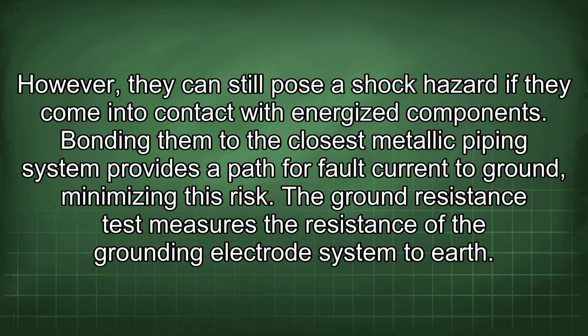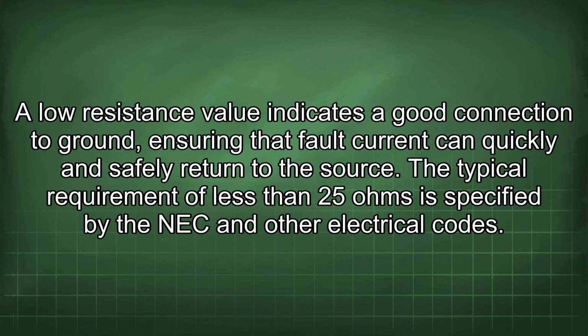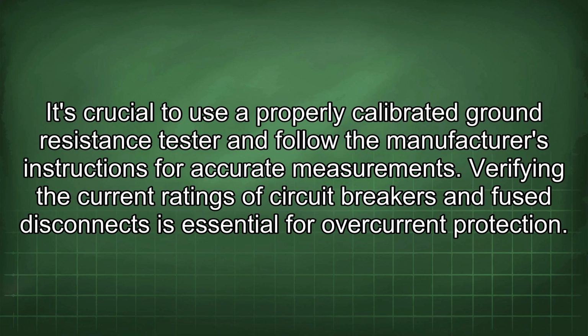The ground resistance test measures the resistance of the grounding electrode system to earth. A low resistance value indicates a good connection to ground, ensuring that fault current can quickly and safely return to the source. The typical requirement of less than 25 ohms is specified by the NEC and other electrical codes. It's crucial to use a properly calibrated ground resistance tester and follow the manufacturer's instructions for accurate measurements.